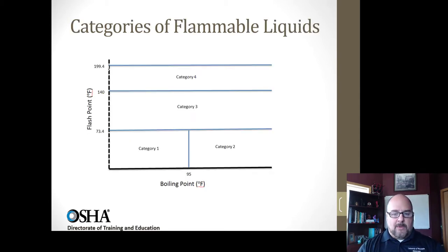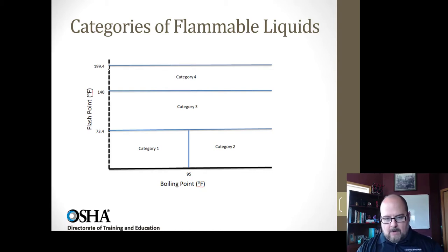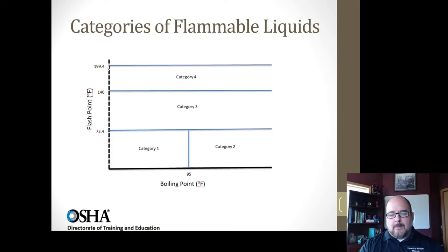The way OSHA breaks down its flammable liquids, flashpoint is the most dominant factor on the left of the chart, and boiling point on the bottom only dictates categories one and two. Category one is the most flammable — it has the lowest flashpoint and the lowest boiling point. Category two has a low flashpoint but a slightly higher boiling point. Then we get categories three and four. NFPA has a slightly different system.